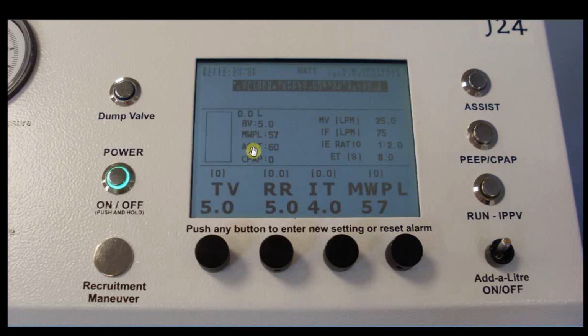Under that we have the assist value, which is currently at 60. This means that in assist mode, which isn't set yet but is controlled by this button at the top here, if the patient was to inhale at a rate greater than or equal to 60 litres per minute, then an assist breath would be triggered. We'll cover this more fully in the video.